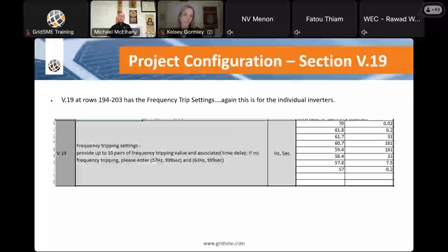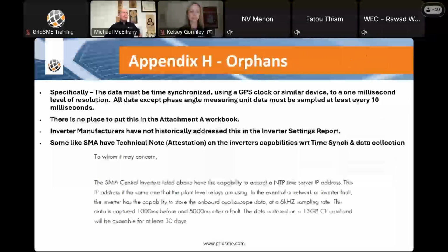The inverter settings report has both frequency and voltage tripping settings, but attachment A only has a place in this V.19 where you can put the frequency tripping settings. So we really try to double check this against the inverter settings report to make sure that the numbers line up. But we also do a quick first cut, not necessarily in engineering all the way to the point of interconnection, but we validate this against the no trip zone associated with PRC 24 today. So just wanted to show that one real quickly.